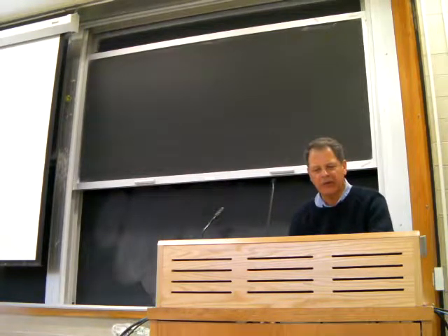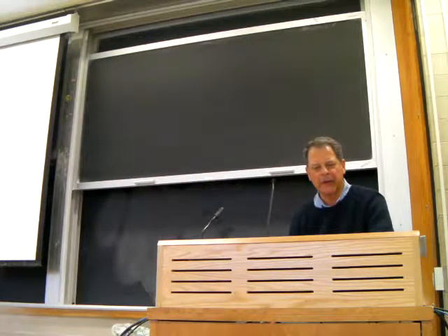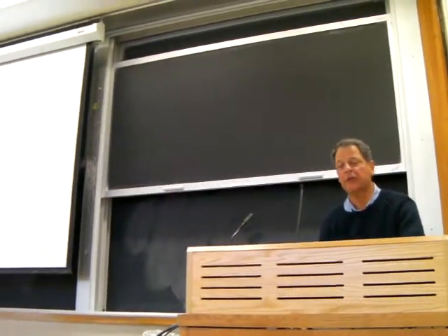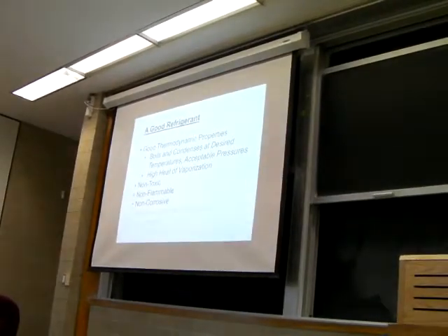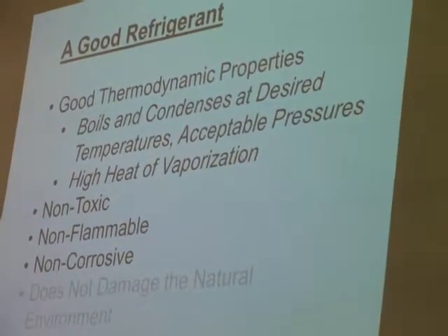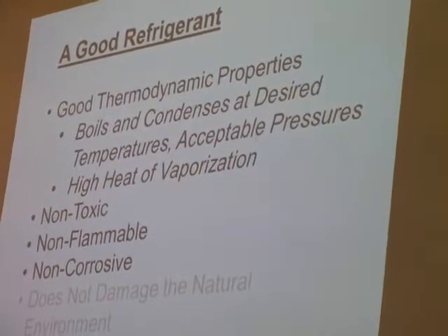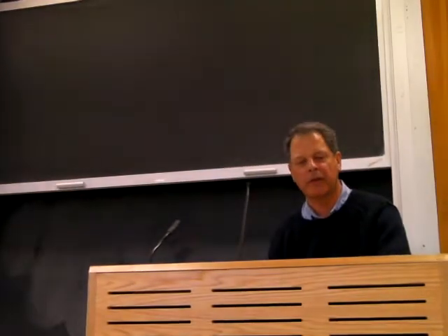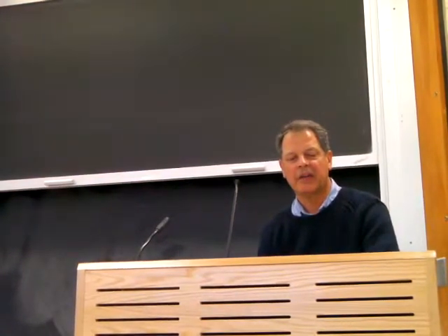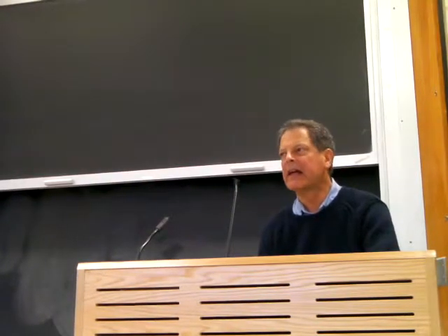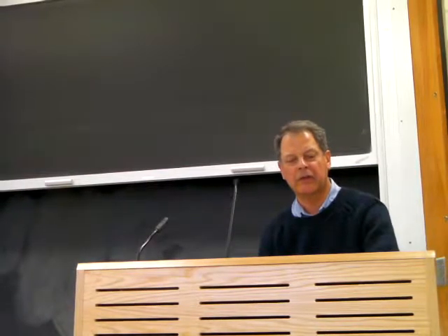I hope you can see the components as you go through here. The fluid — the magic fluid that goes through this cycle, the refrigerant — what makes a good refrigerant? It must have good thermodynamic properties. It must boil and condense at the desired temperatures and acceptable pressures, and it must have a high heat of vaporization — the kilojoules of heat that will vaporize one kilogram of refrigerant, or given off by one kilogram as it condenses. There are other desirable properties: it should be non-toxic, non-flammable, and non-corrosive. And it should not damage the natural environment.